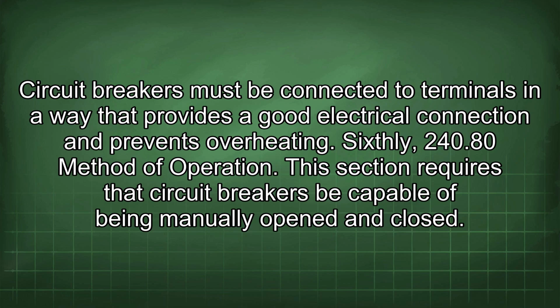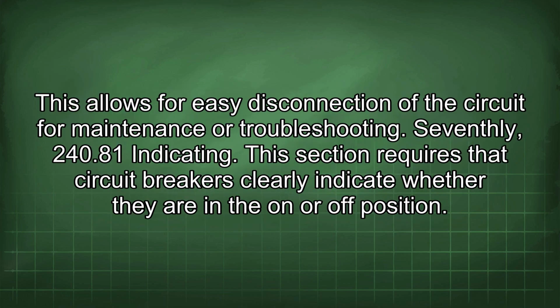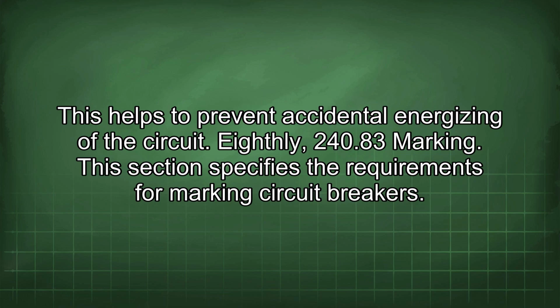Sixthly, 240.80 Method of operation. This section requires that circuit breakers be capable of being manually opened and closed. This allows for easy disconnection of the circuit for maintenance or troubleshooting. Seventhly, 240.81 Indicating. This section requires that circuit breakers clearly indicate whether they are in the on or off position. This helps to prevent accidental energizing of the circuit.